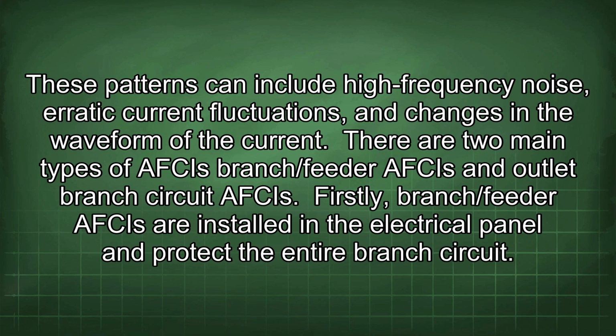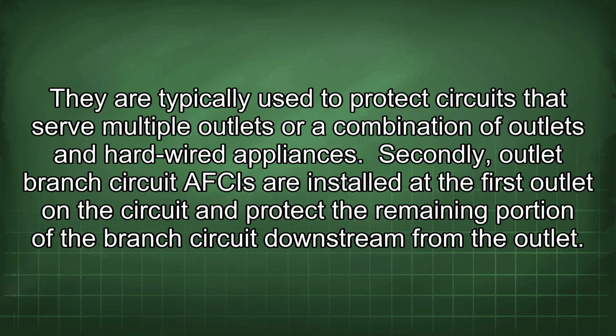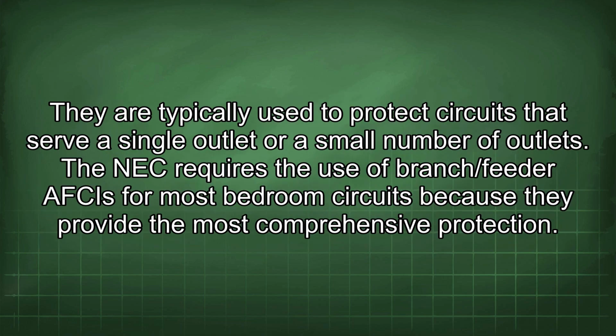There are two main types of AFCIs: branch/feeder AFCIs and outlet branch circuit AFCIs. Firstly, branch/feeder AFCIs are installed in the electrical panel and protect the entire branch circuit. They are typically used to protect circuits that serve multiple outlets or a combination of outlets and hardwired appliances. Secondly, outlet branch circuit AFCIs are installed at the first outlet in the circuit and protect the remaining portion of the branch circuit downstream from the outlet. They are typically used to protect circuits that serve a single outlet or a small number of outlets.